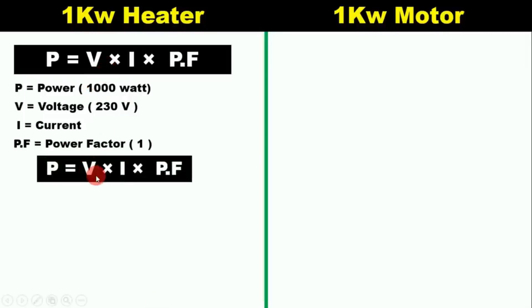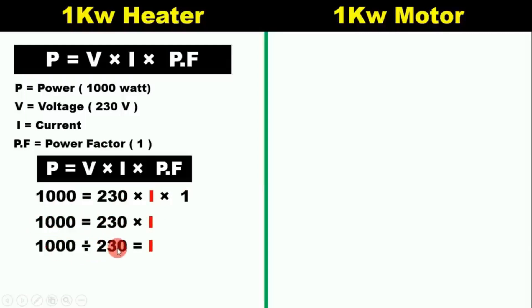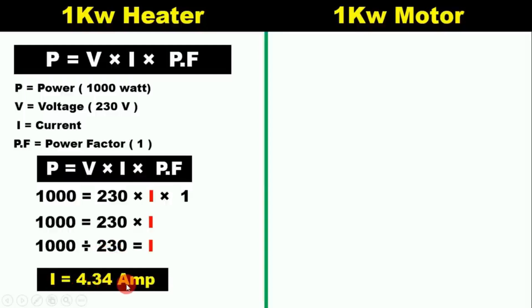Now using this formula, putting in all the values: power is 1000, voltage is 230, we have to find current, and power factor is 1. When we multiply 230 by 1 it remains 230. Now divide 1000 by 230 — we get the value of current as 4.34 ampere. So a 1 kilowatt heater working on single phase power supply will consume 4.34 ampere of current.